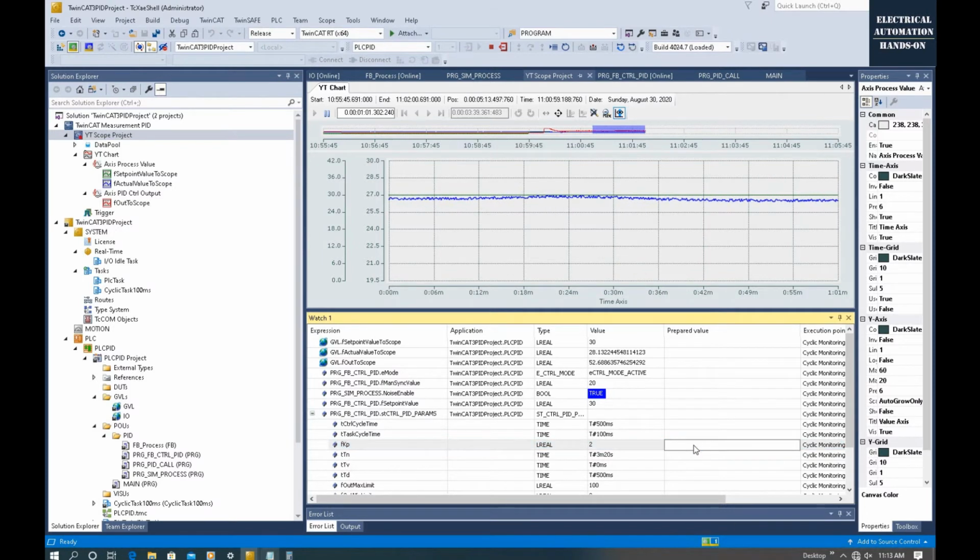So let's set the gain to 6. Even if we increase the gain, it will decrease this error. However, a higher gain will make the actuator very sensitive to the error and to the noise. So we had better set the gain to a certain value, not too high but not too low. That's why I set 6 as the initial value.